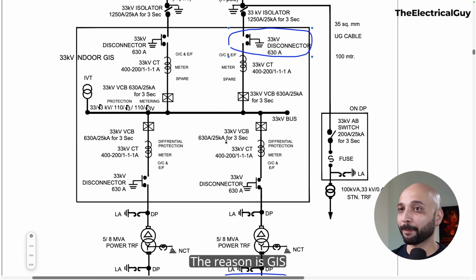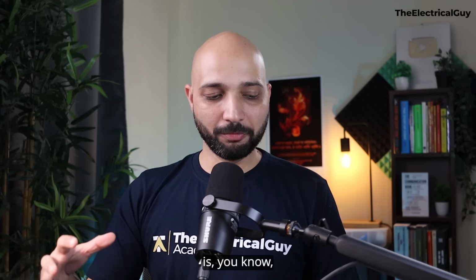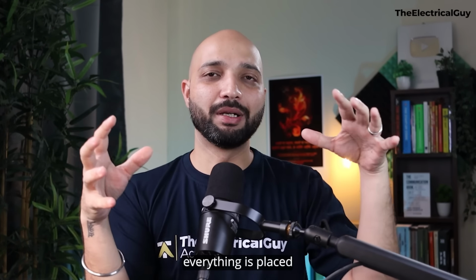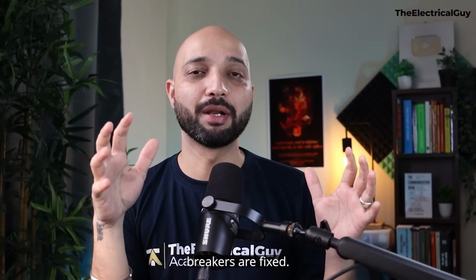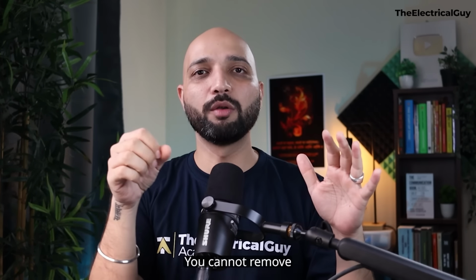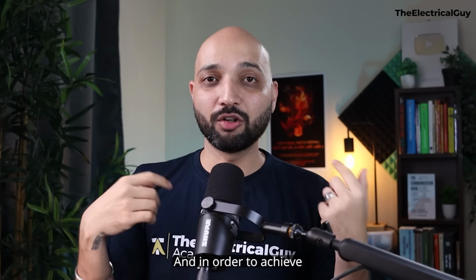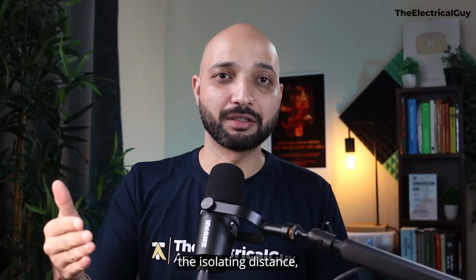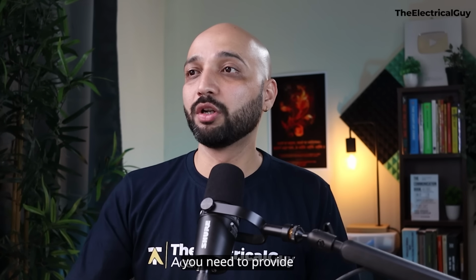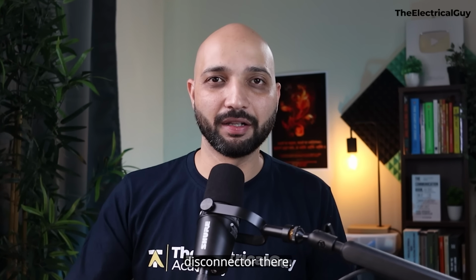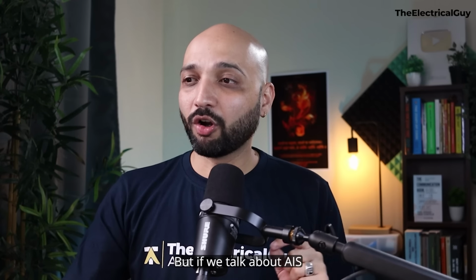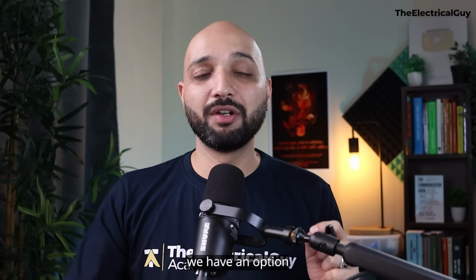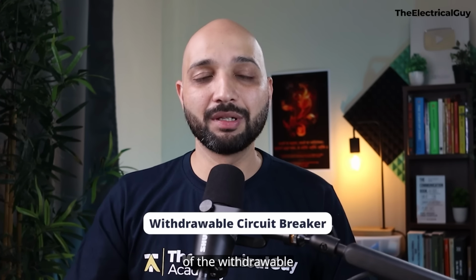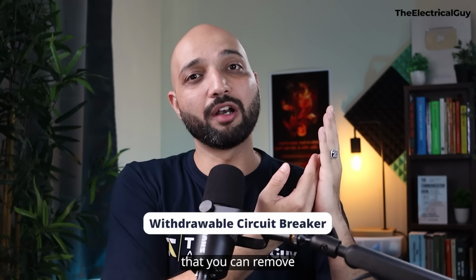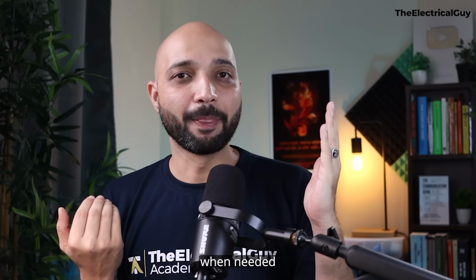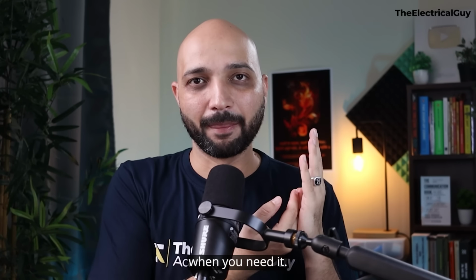The reason is GIS is a tank. Everything is placed inside a tank and circuit breakers are fixed. You cannot remove the circuit breaker. And in order to achieve the isolating distance for safe operation, you need to provide a dedicated disconnector there. But if we talk about AIS switchgear, we have the option of a withdrawable circuit breaker, a circuit breaker that you can remove from the panel when needed and put back when you need it, right?